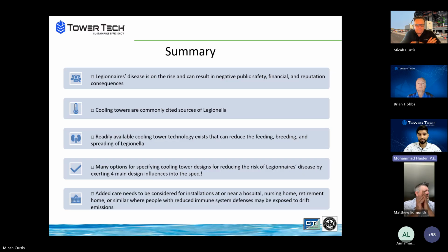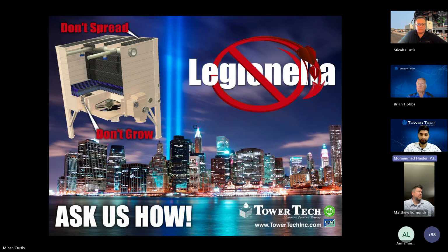Cooling towers continue to be a highly cited source when it comes to the proliferation of Legionella. We're trying to do our best to promote designs that help reduce that. There is cooling tower technology that exists currently that can reduce the feeding, breeding, and spreading of Legionella. They are readily available. And there are many options in specifying a traditional cooling tower design that can reduce the risk of Legionella as well. Keeping all these things in mind, we have to realize that the at-risk and high-risk populations, such as near hospitals, nursing homes, retirement houses, need to be especially thought about when choosing a design that is going to help reduce the risk of Legionella in the surrounding area.